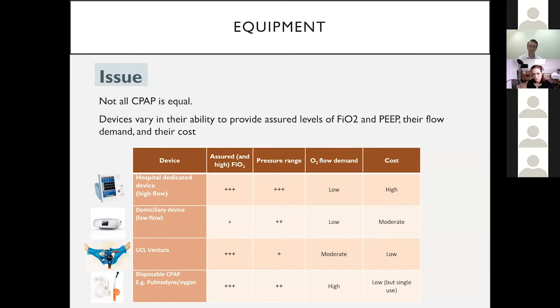Finally, the disposable CPAP kits that we did procure have some advantage in offering a high assured oxygen level with a decent pressure range, and their cost per device is low, although they're single patient use. However, as you'll see in a coming slide, the oxygen flow demand is very high.